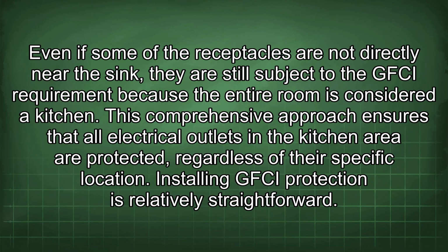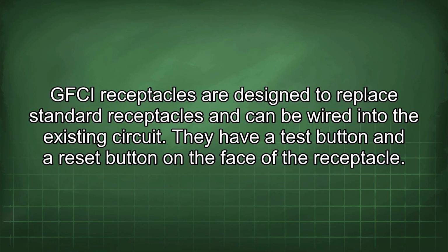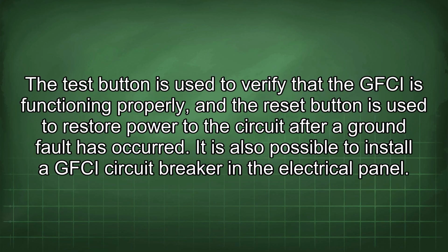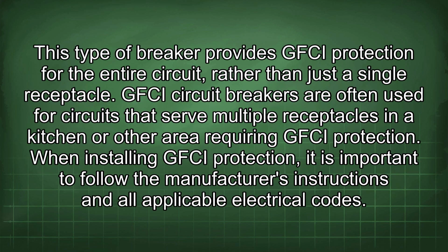Installing GFCI protection is relatively straightforward. GFCI receptacles are designed to replace standard receptacles and can be wired into the existing circuit. They have a test button and a reset button on the face of the receptacle. The test button is used to verify that the GFCI is functioning properly, and the reset button is used to restore power to the circuit after a ground fault has occurred. It is also possible to install a GFCI circuit breaker in the electrical panel. This type of breaker provides GFCI protection for the entire circuit rather than just a single receptacle.